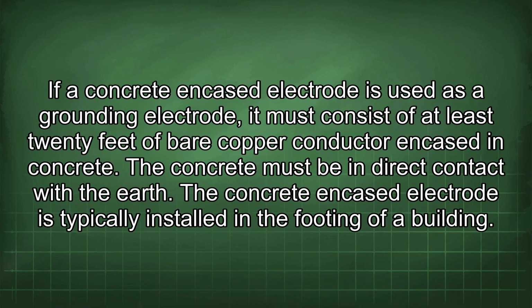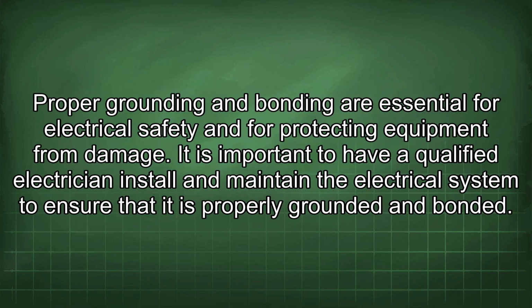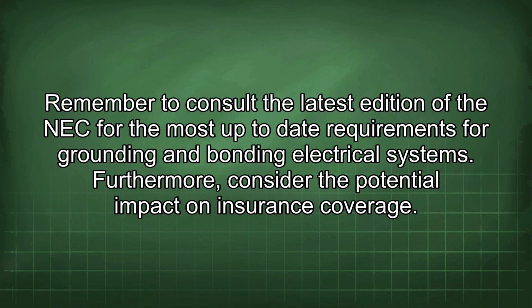If a concrete encased electrode is used as a grounding electrode, it must consist of at least 20 feet of bare copper conductor encased in concrete. The concrete must be in direct contact with the earth. The concrete encased electrode is typically installed in the footing of a building. Proper grounding and bonding are essential for electrical safety and for protecting equipment from damage. It is important to have a qualified electrician install and maintain the electrical system to ensure that it is properly grounded and bonded. Remember to consult the latest edition of the NEC for the most up-to-date requirements for grounding and bonding electrical systems.